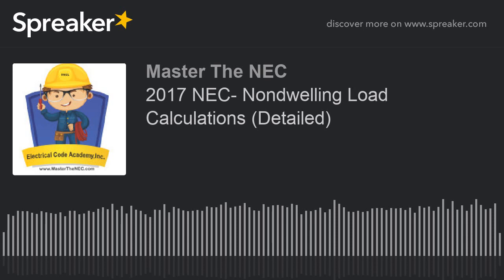All right, so the next thing I'm going to do is go through my list. And again, remember, general use receptacles are not considered continuous load. They are just receptacles for general use purposes. So the next thing I look at is, do I have any fixed multi-outlet assemblies? This is a track, kind of like a plug mold, but a track with individual receptacles inserted into it, and that's called a fixed multi-outlet assembly.